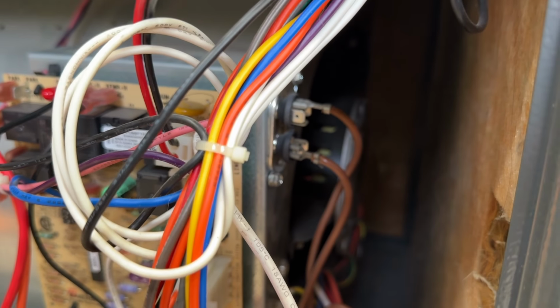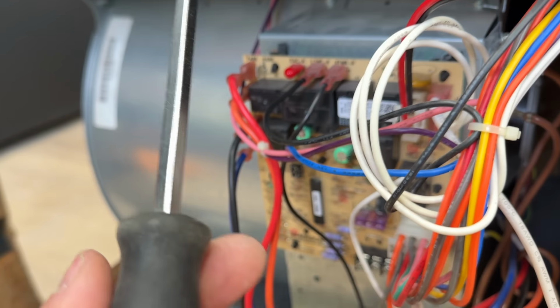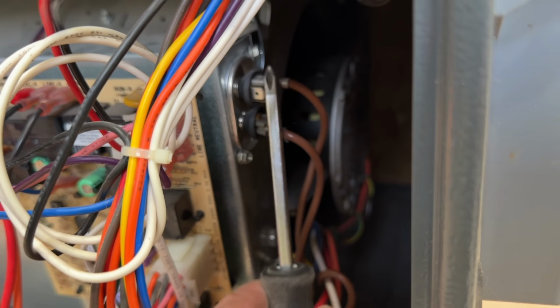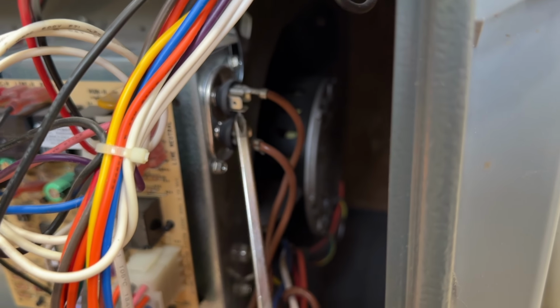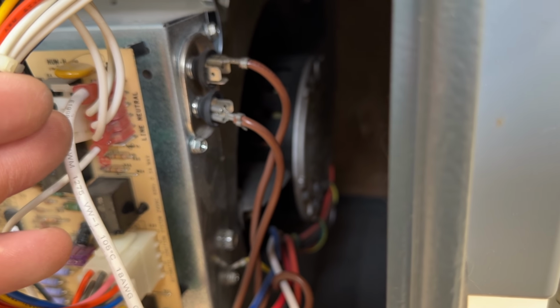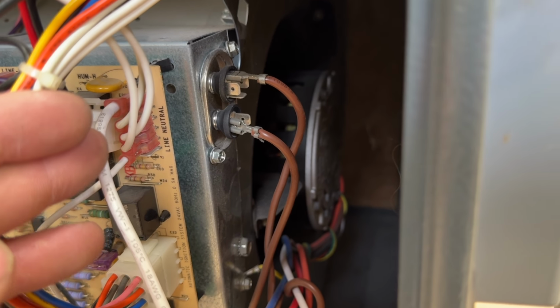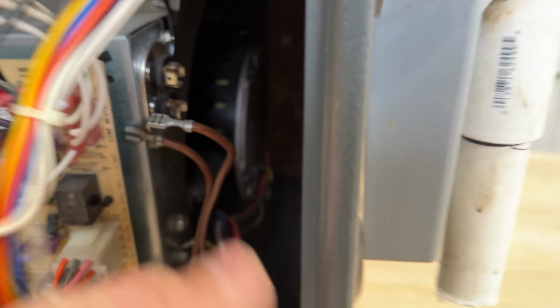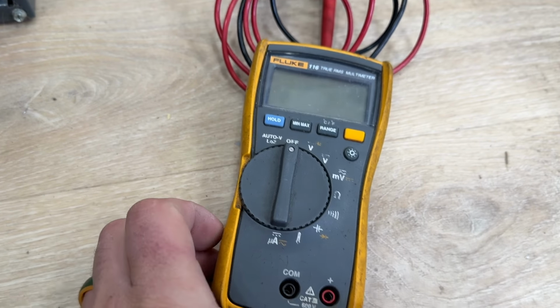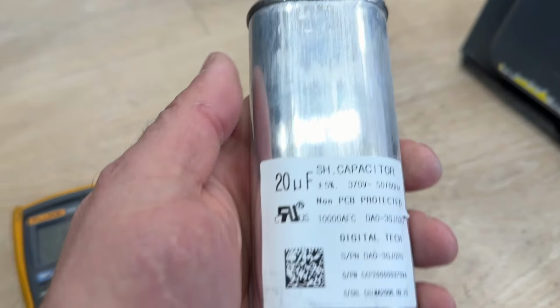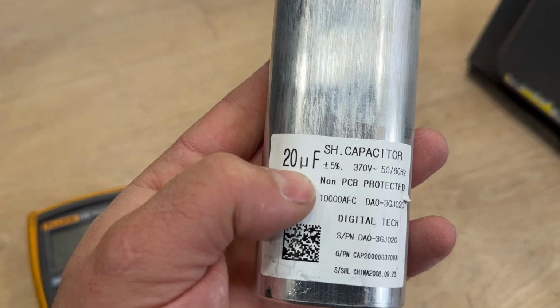So again, make sure your power is completely turned off. And it's very easy to do once you know what you're doing. So you're gonna take an insulated screwdriver and you're just gonna touch these two leads together, and that's going to discharge that capacitor to make sure that you will not receive any sort of electrocution. I've never been popped by one of these. I've heard of some having been popped before, but just be cautious. So next we're gonna pull these leads off, and I'm gonna physically show you how to check this with a voltmeter. Okay, so now that we've got our capacitor pulled out, we can see that it is a 20 UF.